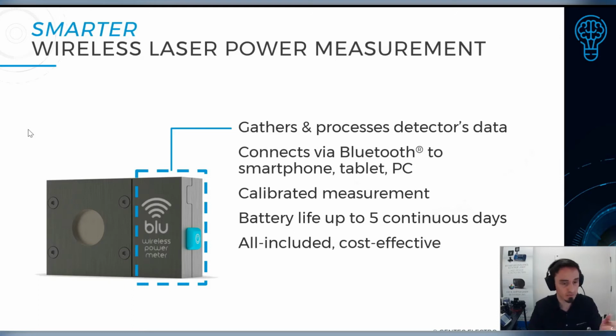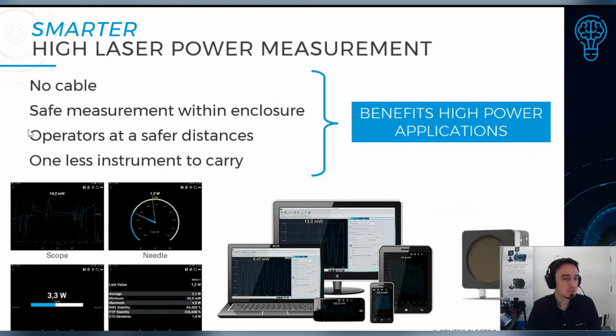You go directly from the device to your PC, for example. Okay, and the new releases last year, we released the high power probes with the blu capability. So that benefits a lot of the high power applications because you have no cable to manage. You can basically set your detector inside your safety enclosure, close the enclosure, run your measurement, and get the calibrated amount of watts to your monitoring devices. So it's safer to operate, no need to run a cable through feed through and everything. And that's once again one less instrument to carry, no interfacing box between the probe and the computer.